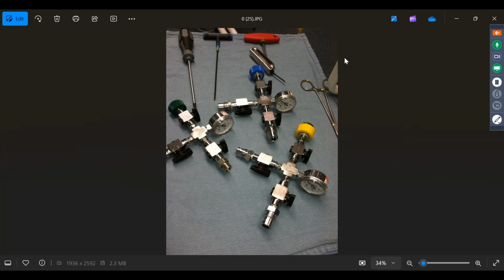So another important thing about an anesthesia machine PM is that the machine doesn't leak. Just as a Jedi must build their own lightsabers, an anesthesia biomed must build their own gas test ports. So air, nitrous, oxygen: I come in to do the PM, I disconnect the machine from the wall, put those in, connect the hoses back up, pressurize the anesthesia machine, then isolate it from the wall, and I look to see if my gauges drop. If my gauges don't drop, I have a tight machine. If I suspect a problem in the hose, this thing has 2 sets of ports on it, so I can loop the hose into it, pressurize it, and see if my hose has a leak in it.